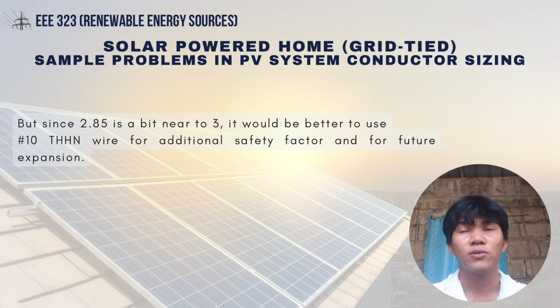Since the initial selected wire is 12 THHN, make a one step higher adjustment. Select initially a number 10 THHN wire. So, VD is equal to 2 times 9.3 times 12.9 times 25 over 10,380 equal sa 0.058 volts. So, total voltage drop percentage natin yung 0.058 over 32.26 times 100%. So, yung total voltage drop natin ay 0.18%.